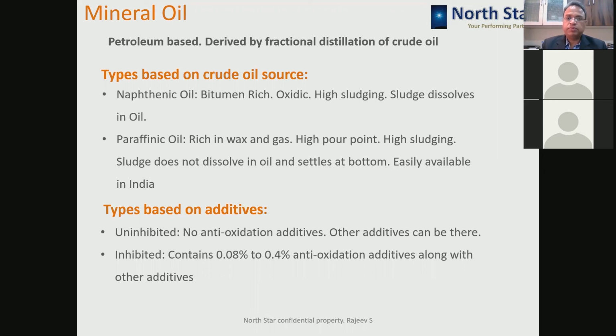Certain additives are added to improve the properties of mineral oil, and the purpose of those additives is mainly to improve the antioxidant properties, improve the pour point, and other similar properties. Based on that, there are uninhibited oils where no antioxidant additives are added. There could be some other additives, like pour point improvers. Inhibited oils are added with antioxidants ranging from 0.08% to 0.4%, and because of this antioxidant material, they are superior in performance against sludging and other oxidation effects.